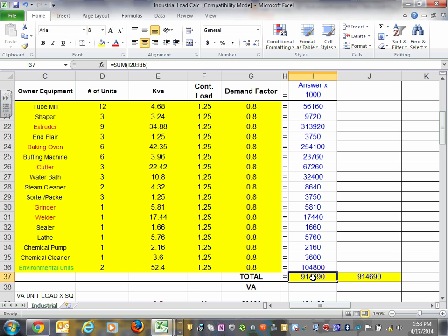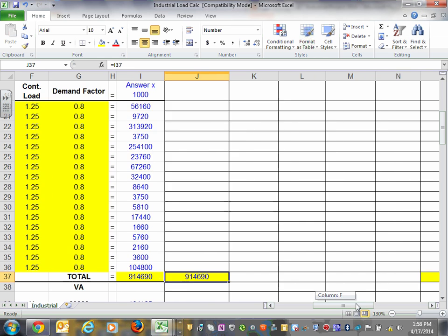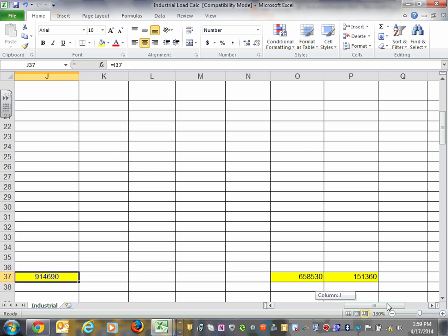So this is the allocated load for the manufacturing process. Nameplate value, add the nameplate value. Then you go here and pull this number, guys, right directly under the switchgear. Remember, J is a switchgear, sizing the service. And as long as you're on it, you pull them under two different numbers here. Now, this is where you're going to use your imagination in Excel. So we're picking all these and assigning them under, which one is that one?